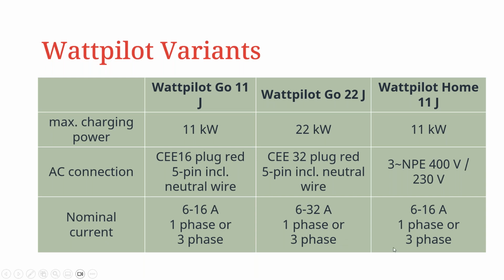And then on the Home variation, it's a maximum size of only 11 kilowatt, 3-phase, so 3-core, normally physical earth, 400 volt, all the way to 230, for example, and then from 6 only to 16 amp. So it's very similar to the Go variation, except it is a physical wall mounted unit.